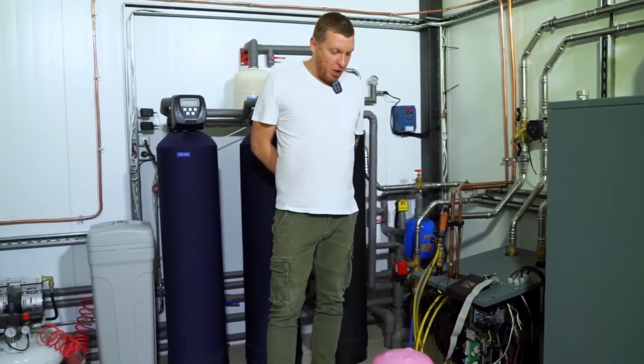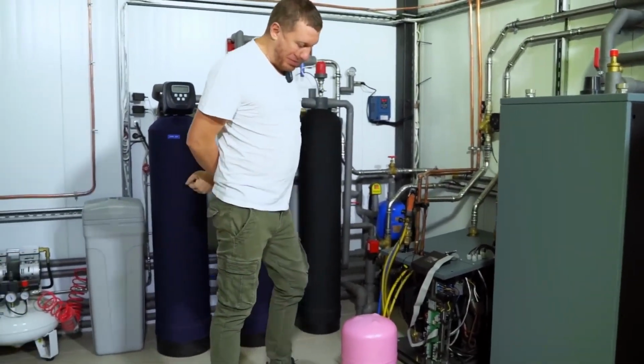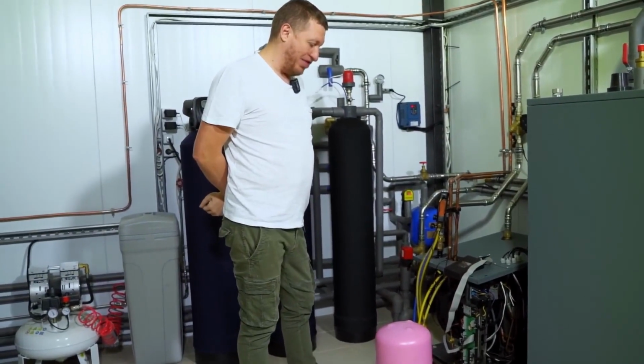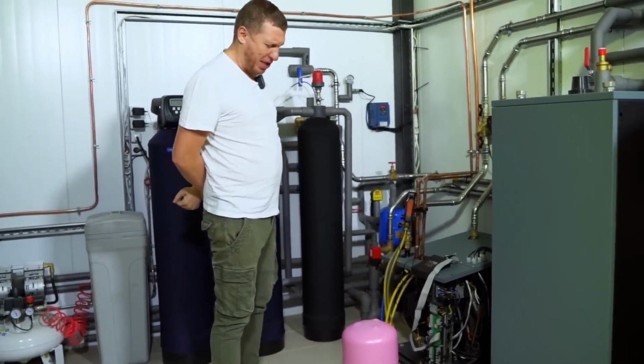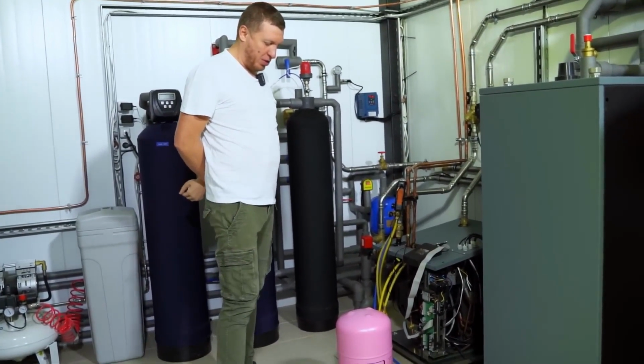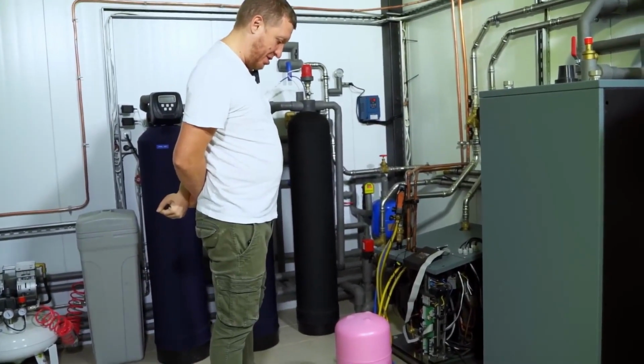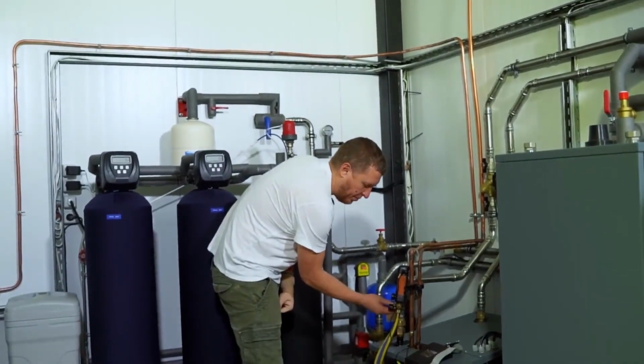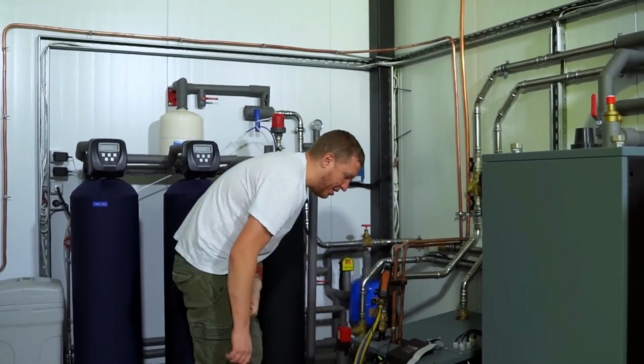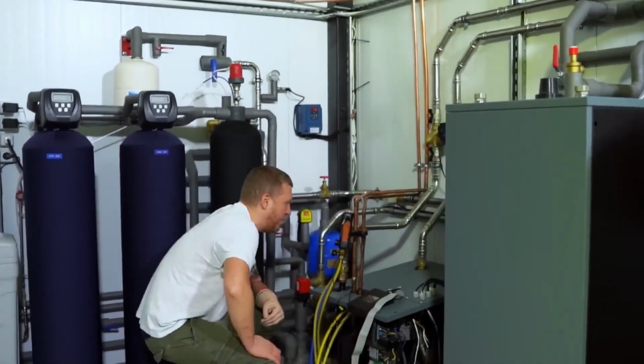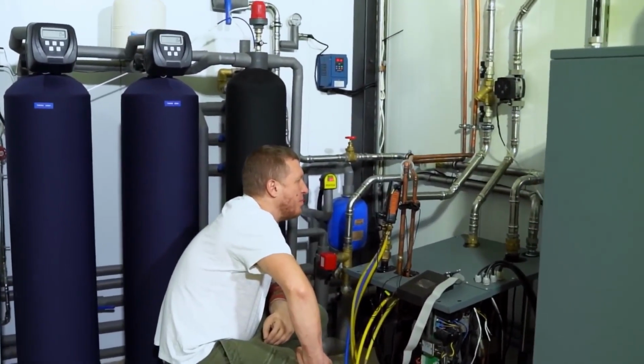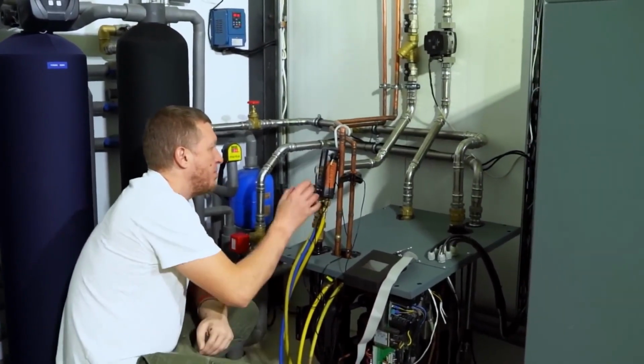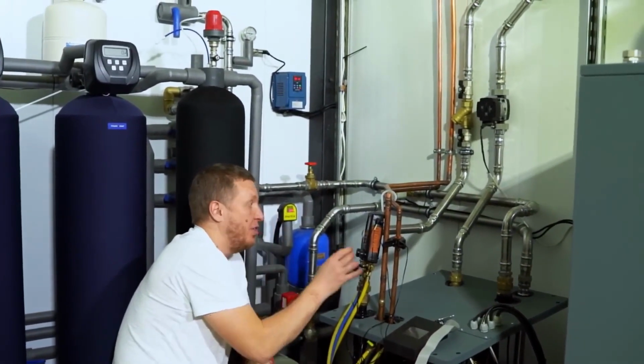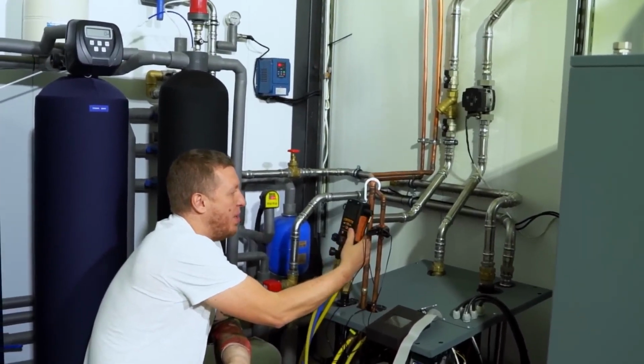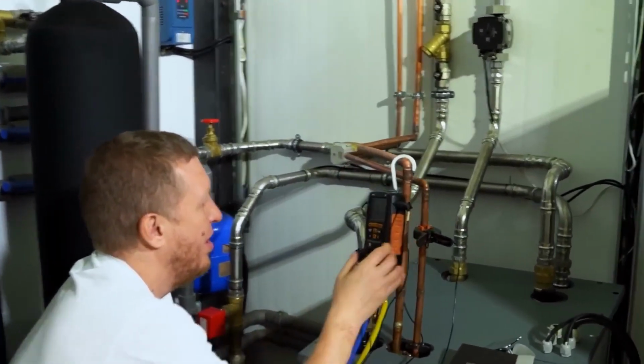When charging through the liquid phase, you have to be careful not to flood the compressor, otherwise you could get a hydraulic shock. It's not as dangerous for a rotary compressor, but still. Alright, we've charged 2 kilograms. Let's see what's happening now. So according to the readings here, look, our evaporation is at 0 degrees. Condensation is at 18, it will stabilize soon.